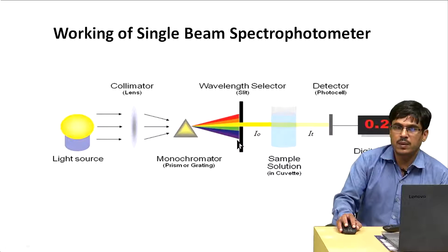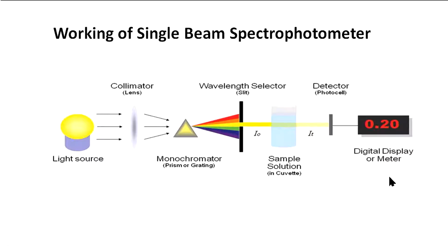The wavelength that is just in front of the opening of the slit will pass through this slit and then strike the sample placed in the cuvette. Here you can see that the light emitted from the prism is of intensity I0. When it passes through the sample in the cuvette, some part of this light is absorbed by the absorbing media, and the remaining light, represented by IT, is transmitted through the sample. It is the light that is not absorbed by the sample. This light then strikes the detector, which converts the intensity of the light into an electric signal, which can be read by the digital display meter.